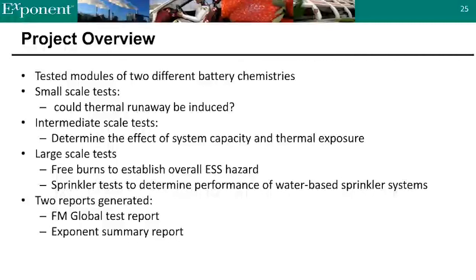Those were followed by intermediate scale tests to determine the effect of the system capacity on the overall thermal hazard, which were then followed by large-scale tests, broken into two categories: some free burn tests to establish the overall energy storage system hazard, followed by sprinkler tests to determine what type of performance would be necessary to control these fires. As a result of this work, two reports were generated. There is the Factory Mutual Global test report that has significant detailed information about the very specific details of the tests, and Ben will tell you where to get that. And then there was the Exponent summary report, which was generated as a summary of the overall project, and that is available on the Research Foundation website.